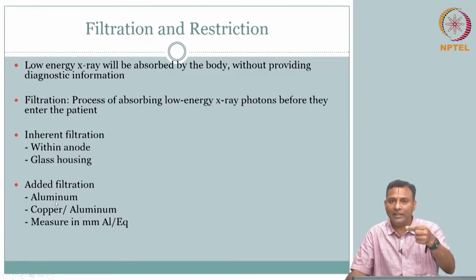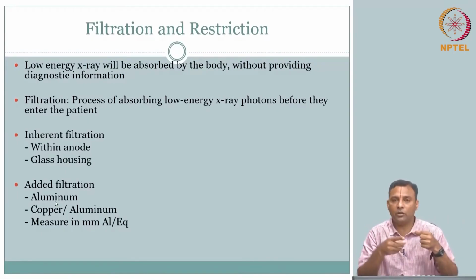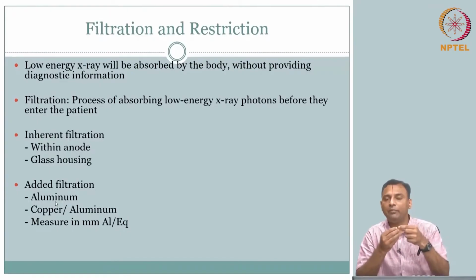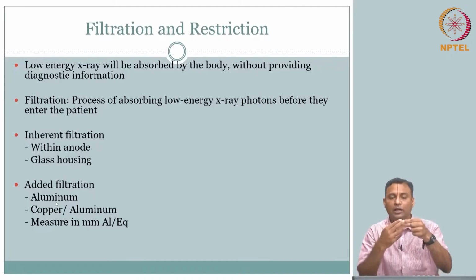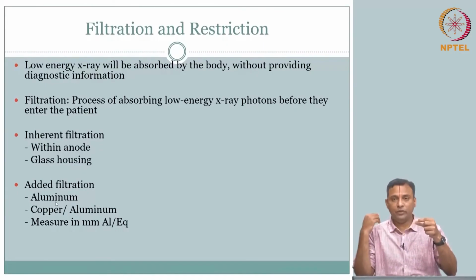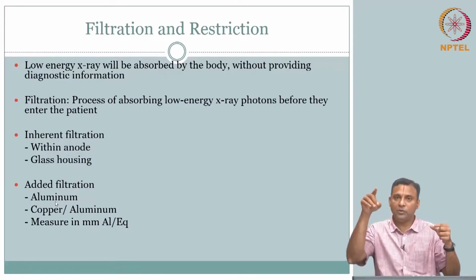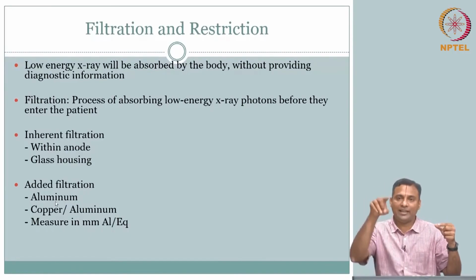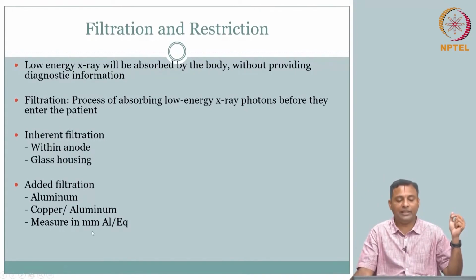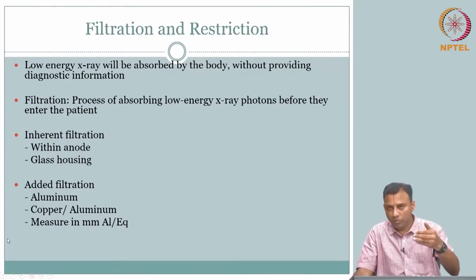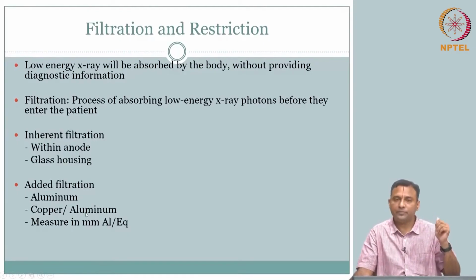So, that means I want a material which can absorb the X-ray energy that is coming out on the lower end. When you mean by attenuate completely, absorb and attenuate completely, so that the other side it does not come through, it has to have e to the power minus mu delta x. So, when I say a material, it has a mu. Now, the only thing is delta x. So, that is your measure in thickness. So, equivalent thickness is always reported. So, aluminum by far is the common. So, 1-2 millimeter thick aluminum sheets are kept in front of the X-ray tube to absorb the low energy.